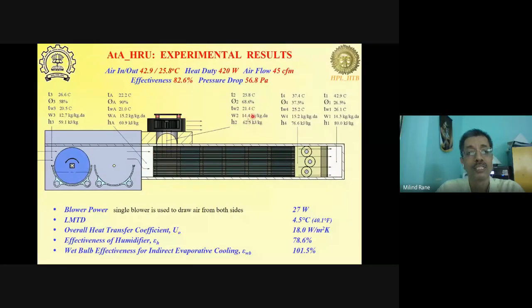And the media used to cool this was essentially, now when this air goes into the conditioned space, an equal amount of flow would be displaced from the conditioned space. And that conditioned space, in this particular example, was maintained at about 26.6 degrees centigrade and 58% RH, typical indoor air conditioned conditions for an office or things like that. So if that is the input to this, then it would be humidified first using the rotating contacting device, another one of our patents here, and then that would cool down to 22 degrees centigrade as it gets humidified as it passes over the rotating disc. Now, this would increase the humidity level to about 90%. You can notice that the humidity level has gone up from 12.7 grams per kg of dry air to 15.2 grams. This is not kg, this is grams per kg of dry air.